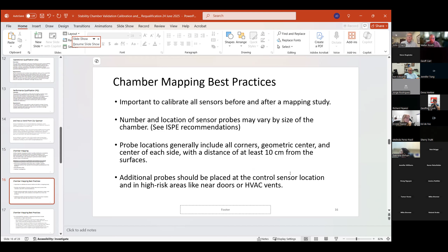For photostability chambers, mapping should also include consideration of light distribution. For ICH Q1B option 1 chambers, that might just be a requirement for a single point determination of radiation intensities using a visible light meter and UV meter, and then verifying the uniformity throughout the horizontal surfaces.